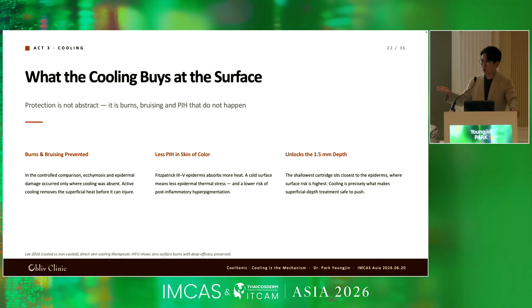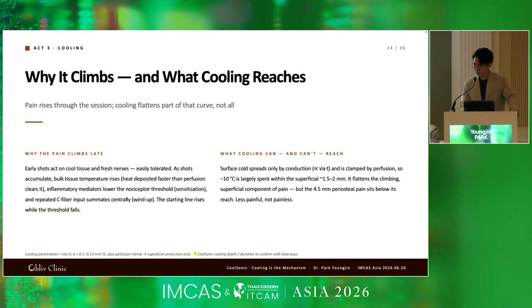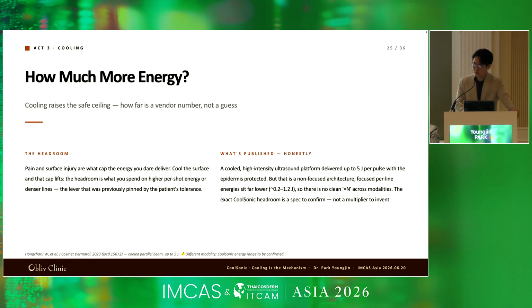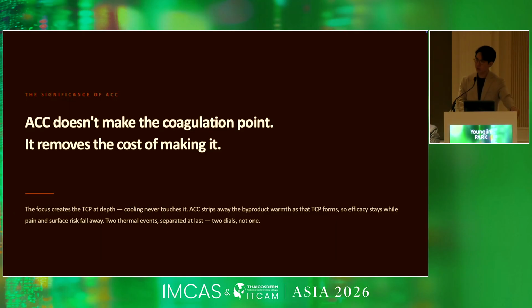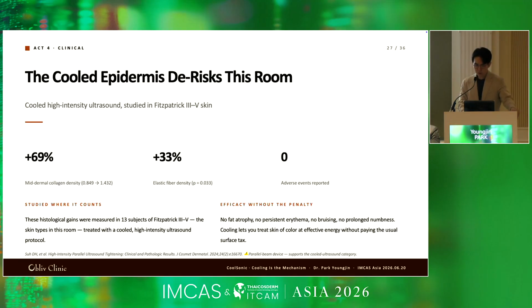But when there's cooling, this will be decreased, meaning that you can use a higher power, especially for 1.5 or maybe 2.0 for the dermal layer to enhance the dermal thickness. So the cooling will help to decrease the climbing of the temperature of the tissues that you haven't treated. And so you can use more energy, or maybe you can use the right energy. You don't have to decrease the energy when the shots accumulate. So ACC does not change the coagulation point, but it will decrease the complication and the pain sensation that comes after. And the cooled epidermis also de-risks the treatment, and the efficacy is still there.